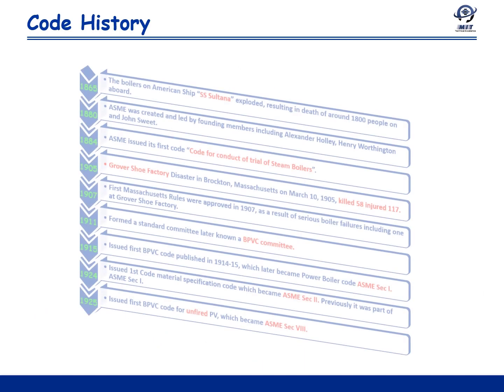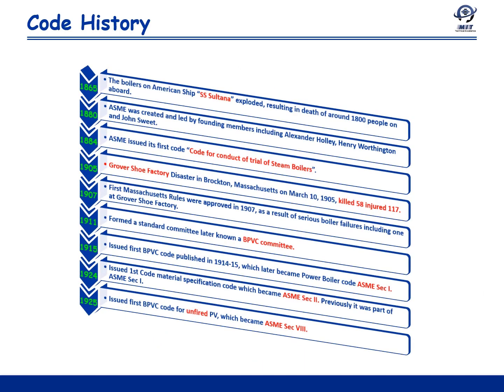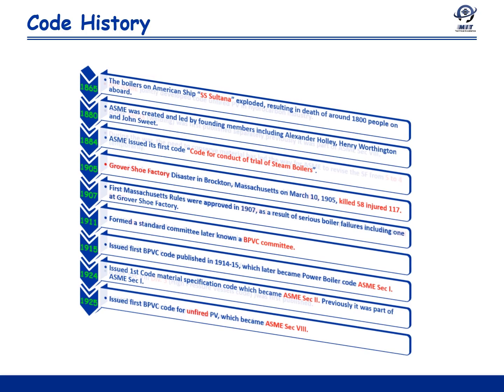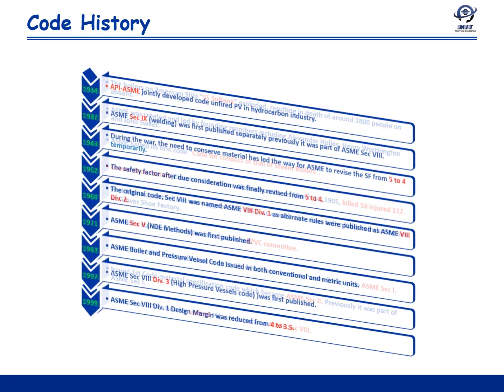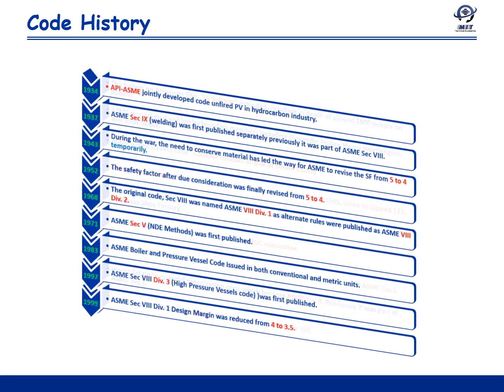Finally, ASME Section 8 Division 1 design margin was reduced from 4 to 3.5 in the year 1999 — the last time the safety margin was reduced. Currently, due consideration is being given to reducing the safety factor even lower, from 3.5 down to 3.